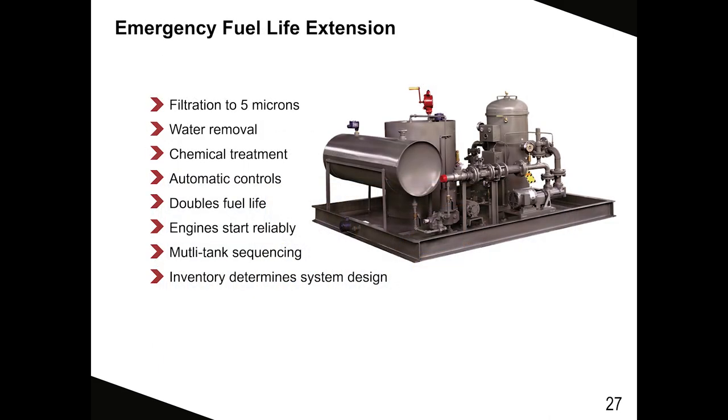Large custom skidded filtration systems used in systems of multiple tanks include filtration to 5 microns, water removal, chemical treatment, and automatic PLC controls for sequencing multiple tanks.